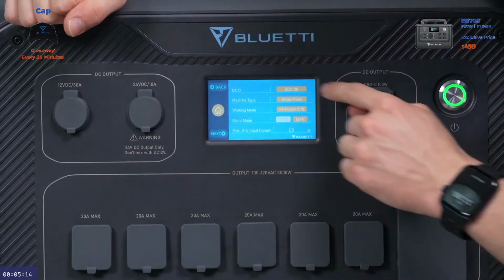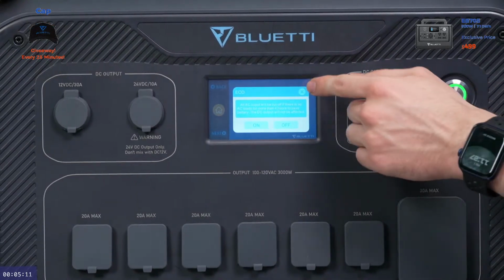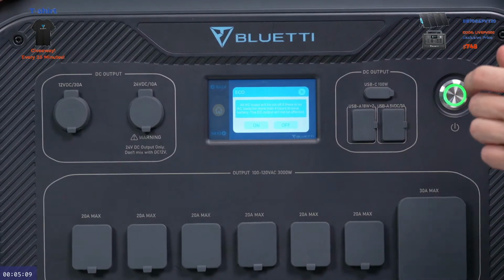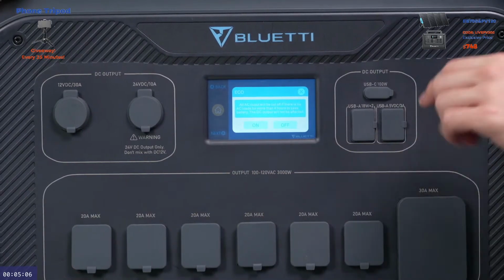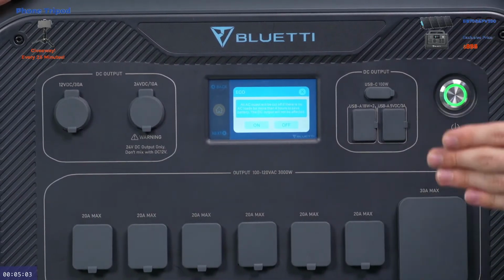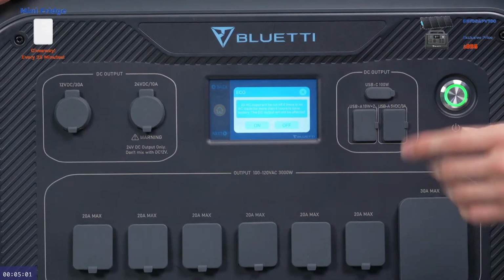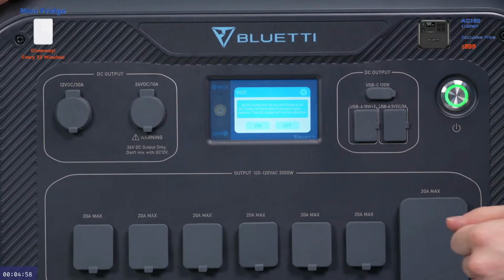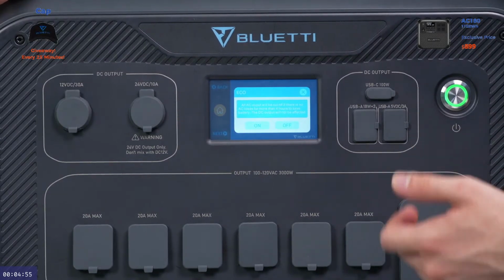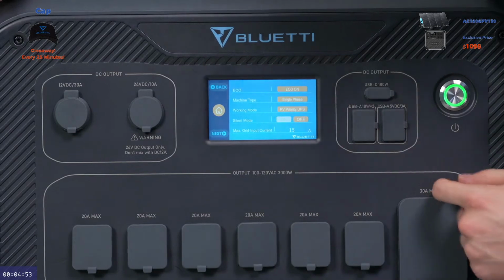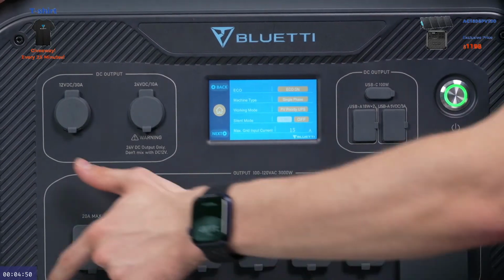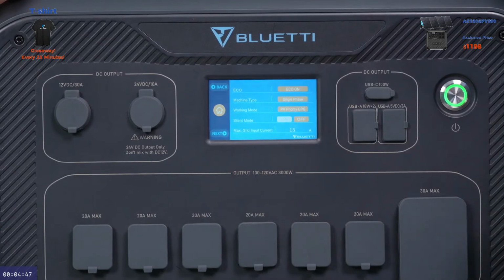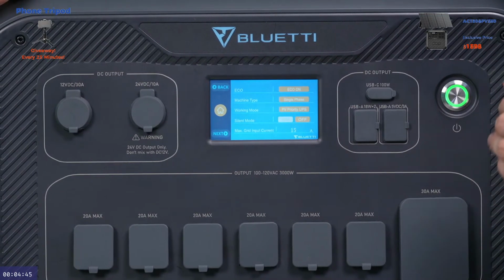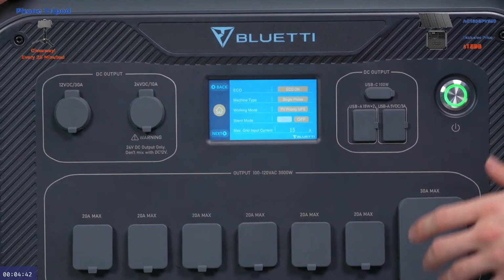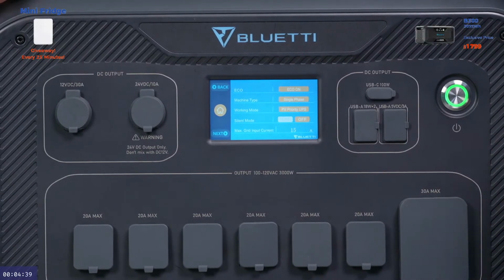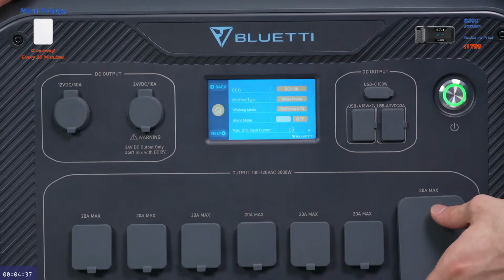Okay, let's go to next, eco mode. Eco mode, as it explains right here, only affects AC outputs without affecting DC, and the time here is fixed at 4 hours. If you have eco mode on - it's very easy to enable, just click this button - now it's on. It will turn off your AC inverters in 4 hours if there is no load or if the load is very low. I'd recommend you guys keep this mode on, because we have a very powerful 3000 watt AC inverter here with some really powerful outputs.